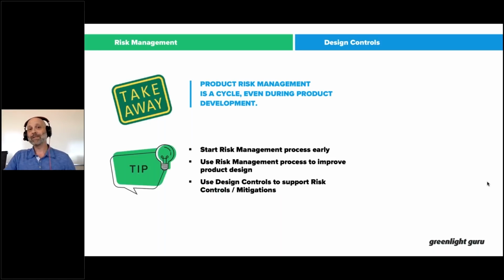My advice to you is to shift to the ISO 14971 camp because of how important that is and how recognized that is by FDA, by EU, by Health Canada, by TGA in Australia, basically by every regulatory body in the world in the medical device industry. They recognize ISO 14971.